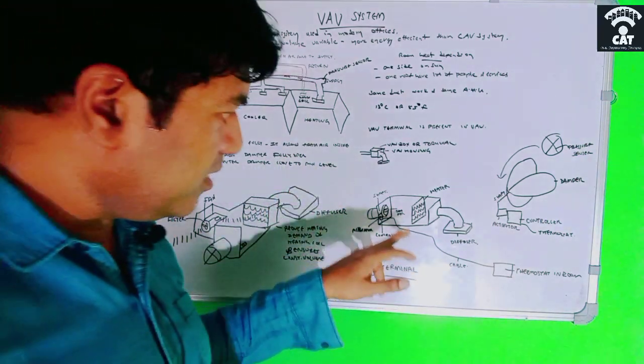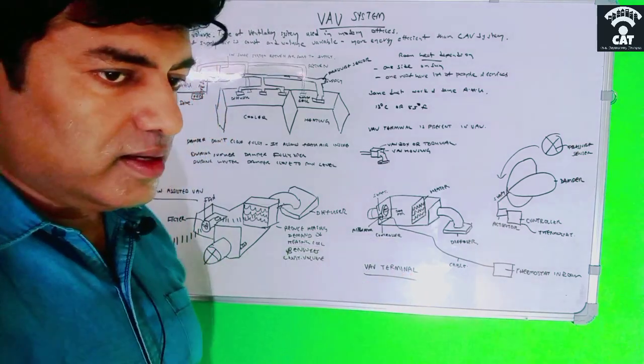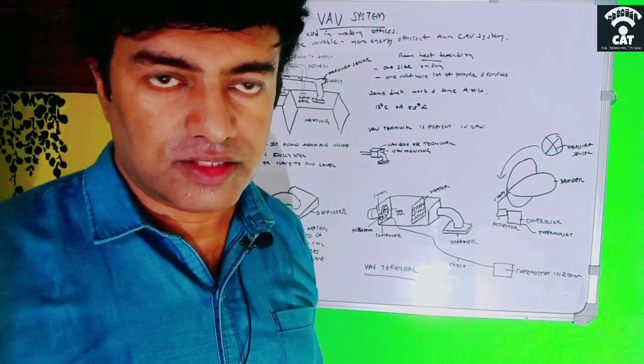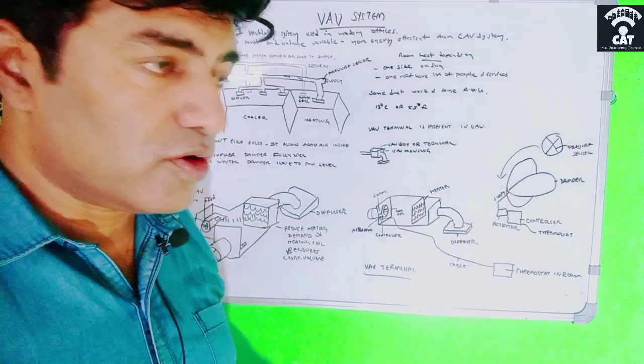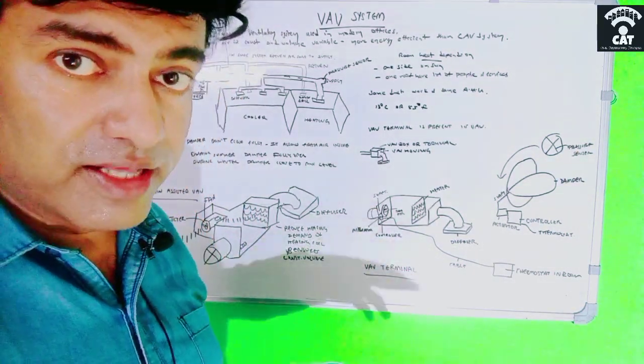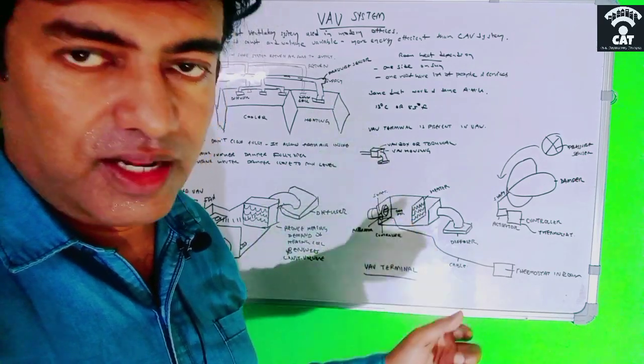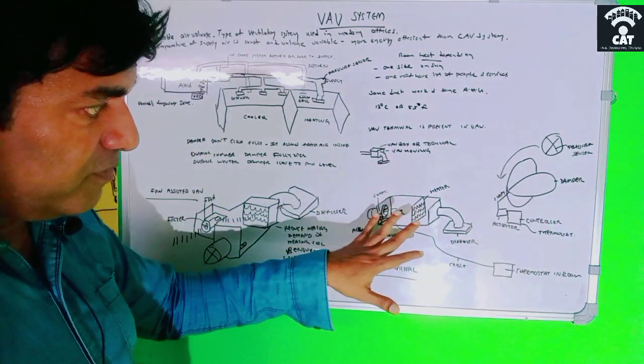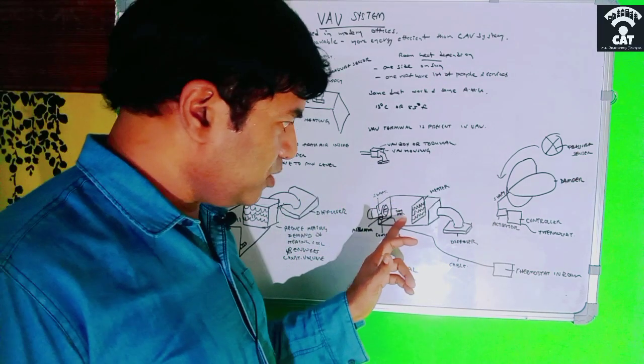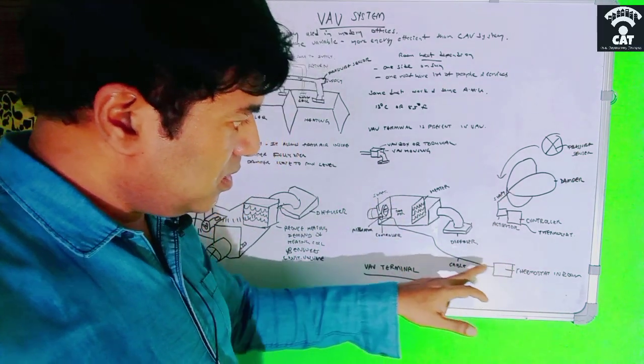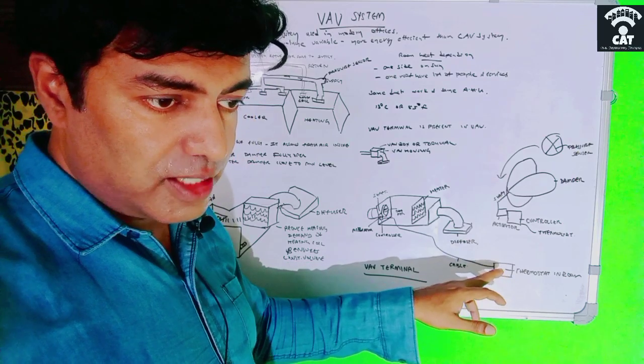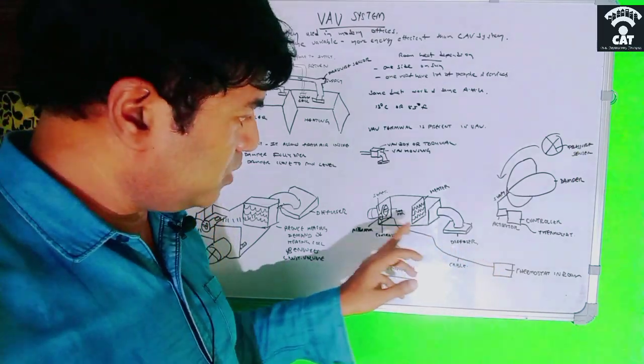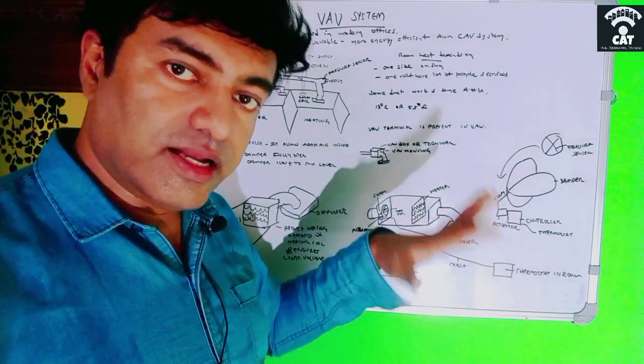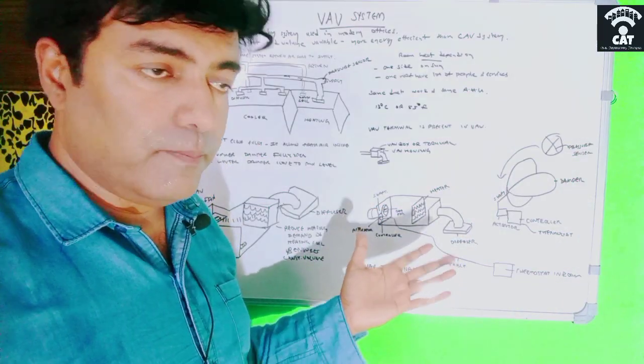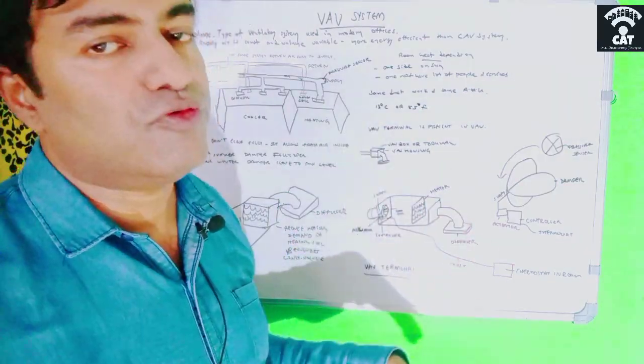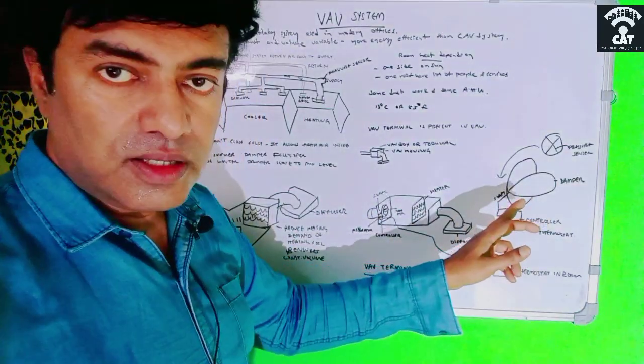Similarly, in VAV, in some cold countries, or maybe even at winter time, we can go for a VAV terminal which is fan assisted, which is called a fan assisted VAV terminal. So this is the usual VAV system. Now we will explain more into it. I told you that the temperature recorded by the thermostat will send a message to the controller, and it will control the cold air supply with the help of closing or opening of the damper. I think you understood that much.